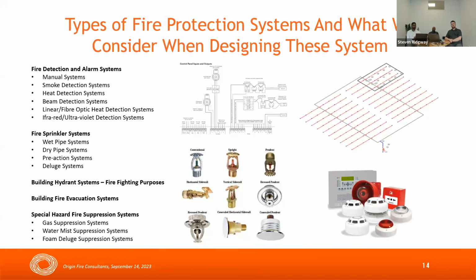Fire sprinkler systems. When designing fire sprinkler systems, we need to consider the storage, the fire load, the rate of fire spread and development, and the extent of potential fire spread in the building or an area. This ultimately determines the classification of occupancy and how much water, typically referred to as the density of discharge or design flow, is required within a particular area to control that fire. We also need to determine the type and size of sprinkler head and the location and coverage of these sprinkler heads for a particular classification of occupancy.